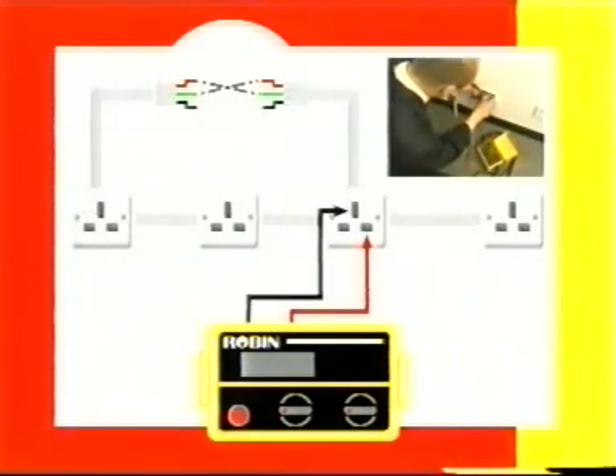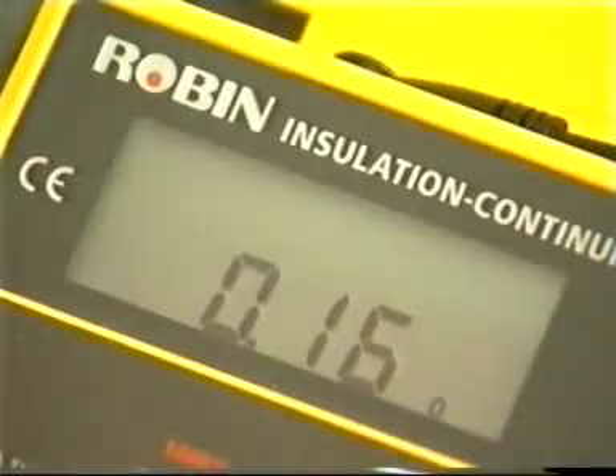A temporary connection is now made between the ends of opposing phase and protective conductors at their origin. Tests are carried out between phase and protective conductor terminals at each outlet. The highest recorded instrument reading will be the circuit contribution R1 plus R2 to the system phase earth fault loop impedance ZS.